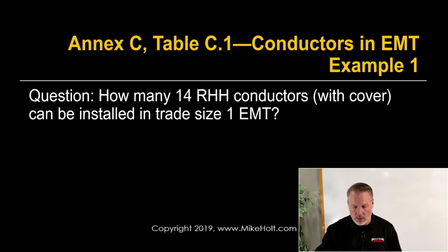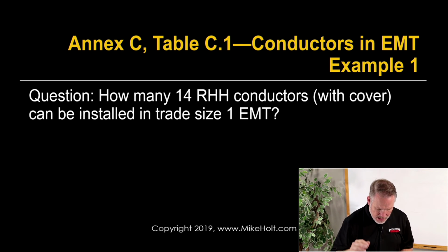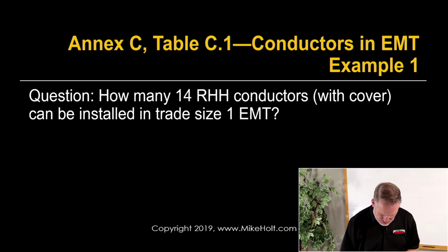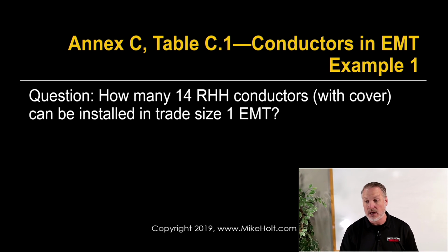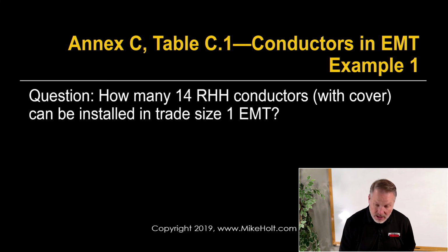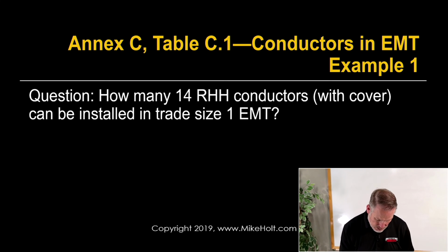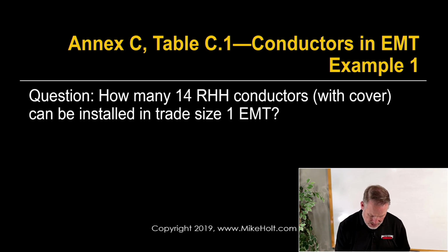So we're just going into Annex C, and we're going to flip the page to page 774. If you look at the top, it says EMT. Is that what we're looking for? Yes, EMT. So we're on the right one. Now we're going to go to a number 14, RHH. So we find RHH, that's the first thing on the page. We go to number 14. And we go over to 1 inch, and it says how many?